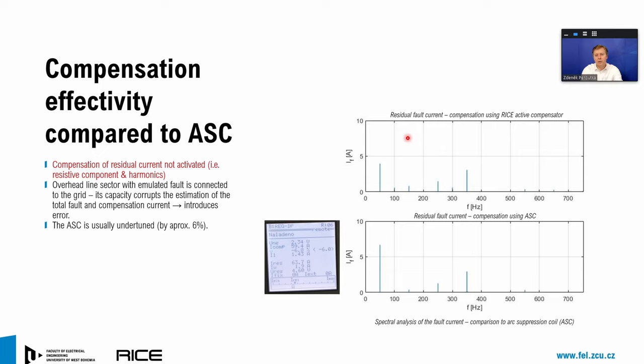And we were unable, because, as I explained, we are identifying the grid impedance in real time under no fault conditions. So we were unable to exactly identify the total grid impedance due to this missing part of the grid. Therefore, our compensation current was not fully optimal. Even under these unfair conditions, our device, this is the upper figure, significantly outperformed the arc suppression coil. The final current was half of the residual current for the optimally tuned arc suppression coil.